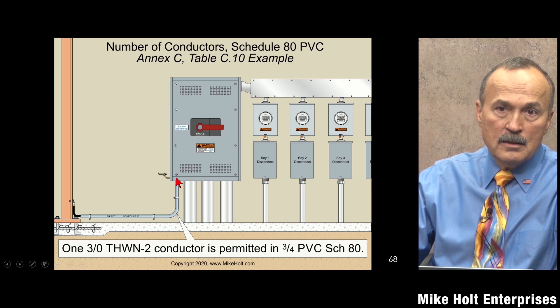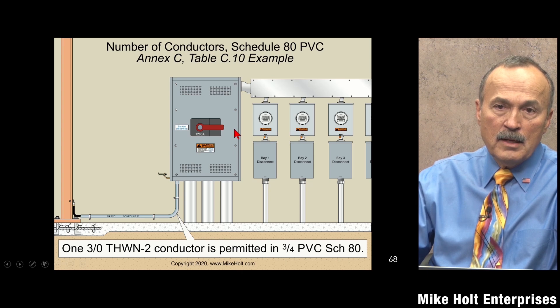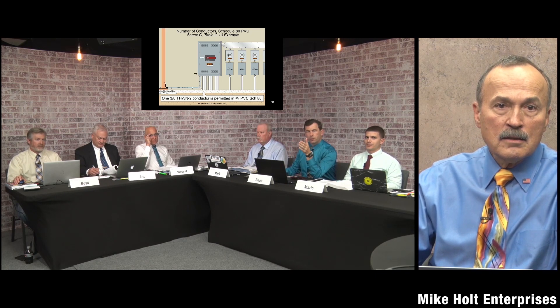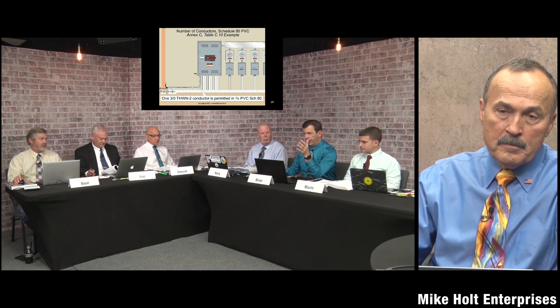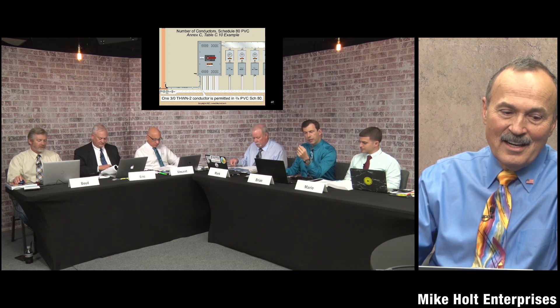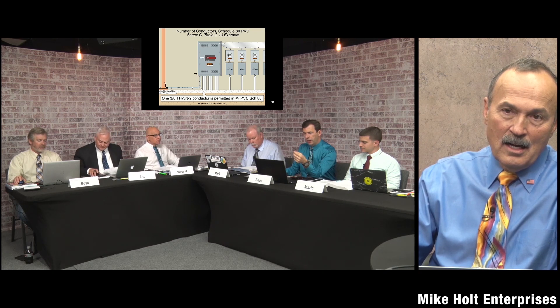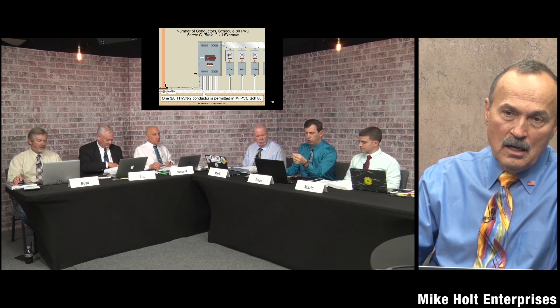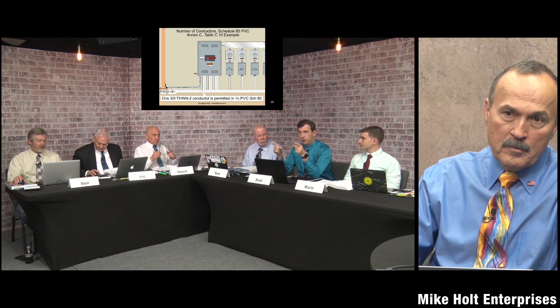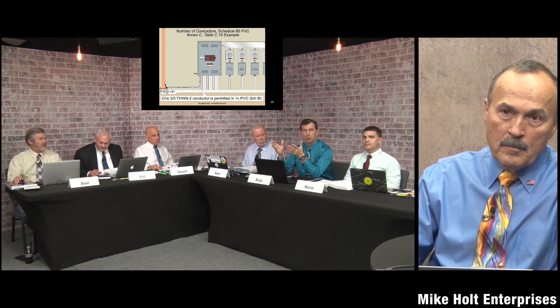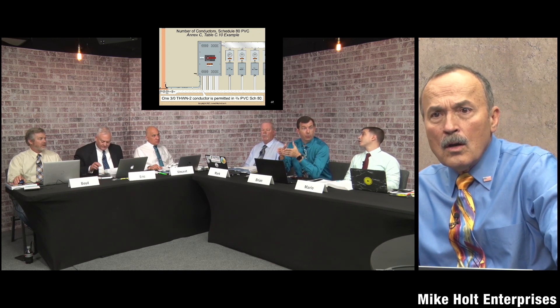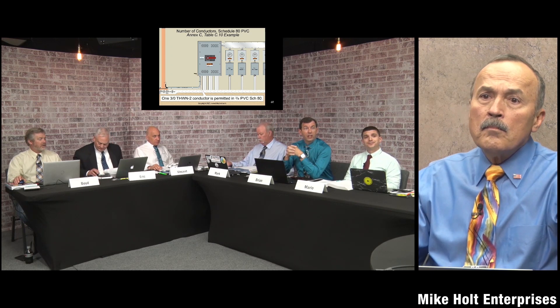When Note 2 says we don't have to limit ourselves to the percentages in Table 1, it's a common application - leave that example in the book. Looking at Note 4: the 24-inch nipple rule applies where conduit is installed between boxes, cabinets, and similar enclosures. A chase pipe running out of a panel going up isn't really the 24-inch nipple rule - that would be considered a sleeve.